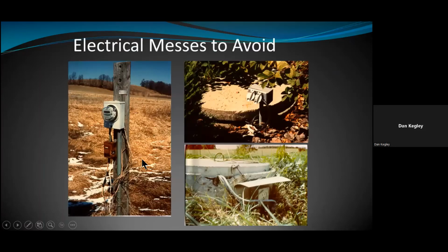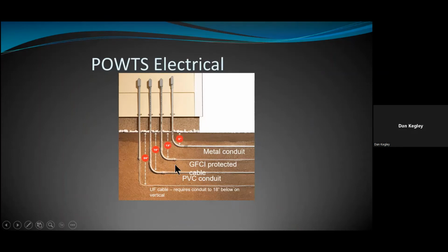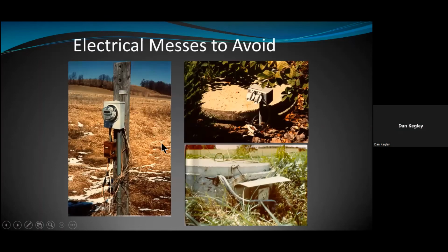And then of course, bushings on the end, like we talked about earlier. And then like a frost sleeve or expansion fitting or slip sleeve to protect from that frost movement. So you can see here, there's just wiring hanging out and those kinds of things. Definitely not the way to have a good installation there.